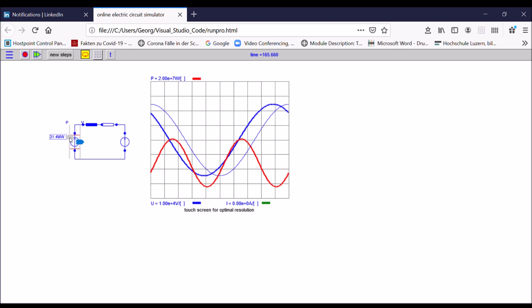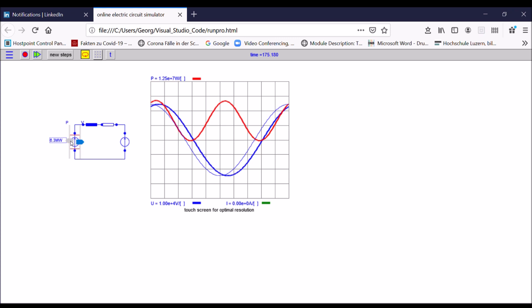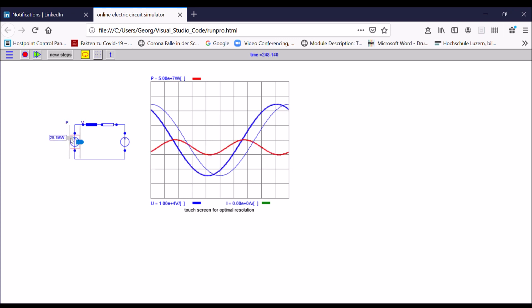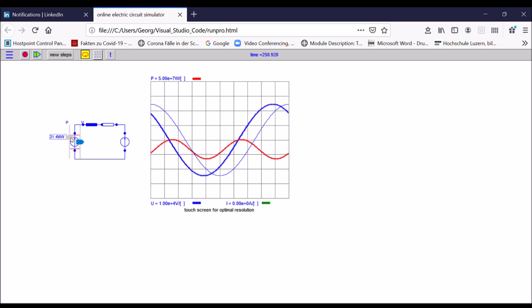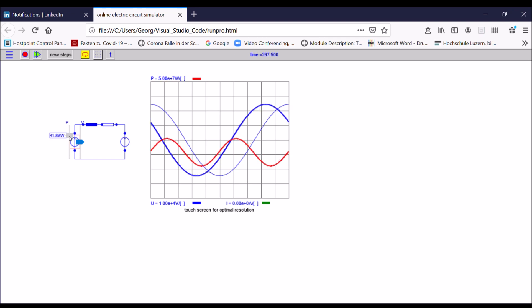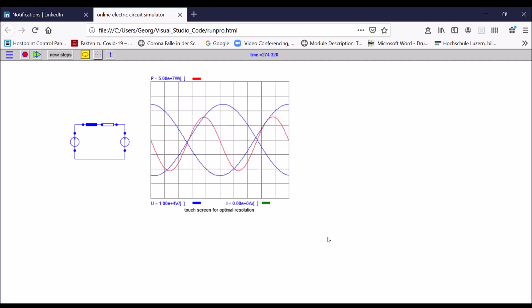This is exactly what happens when you deliver power from a generator to a grid: you get a phase shift between the two voltages. This is how you control power from the generator to the grid. You can operate the synchronous machine as a generator, or if you reverse the torque in the other direction, it operates as a motor. The more I increase the torque, the higher the phase shift between the grid voltage and the induced voltage of the generator will be. I increase the torque until the phase angle between the two voltages reaches 90 degrees. At 90 degrees, I have the maximum power — more is not possible — and if I pass 90 degrees, I lose synchronism, which is a very difficult and dangerous situation for the generator.